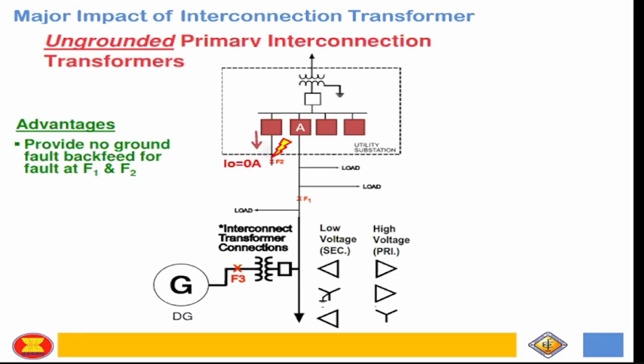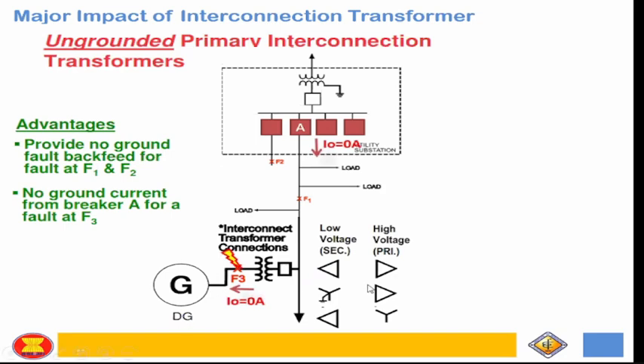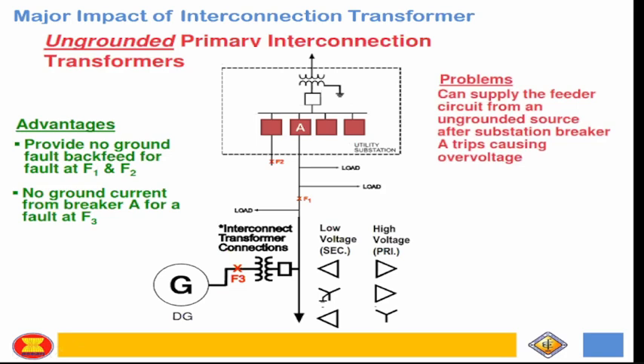But in this case, since it's ungrounded, we can consider na walang zero sequence current on that type of configuration. Then no ground current from breaker A for a fault at F3. Okay? So kung may fault dito, since it's ungrounded, isolation, so yung coordination mo ngayon at the load sides is hanggang dito lang. Okay? So you need not coordinate yung protective device dito to the primary protection, high side breaker, or to the substation. So yun yung advantage niya. But the disadvantage, okay: can supply feeder circuit from ungrounded source after substation breaker A trips. Kung magti-trip ito, okay? And then this is a sustained fault. Since it's ungrounded, yung healthy phases mag-shift into overvoltage.